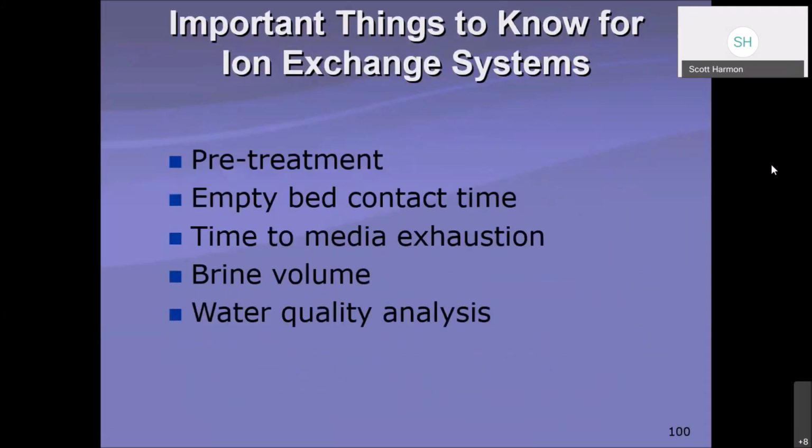So, like any other treatment process out there, there are some important things to take under consideration here. Pre-treatment: if the influent waters are not within the parameters that the ion exchange works best for, you may require some pre-treatment. Again, empty bed contact time, so it has to have a certain amount of time for the arsenic particles to exchange for the salt-based particles. The time of media exhaustion, how long before you're going to have to regenerate your bed, the amount of brine and whether it needs to be replaced, and of course, your water quality analysis is always important.